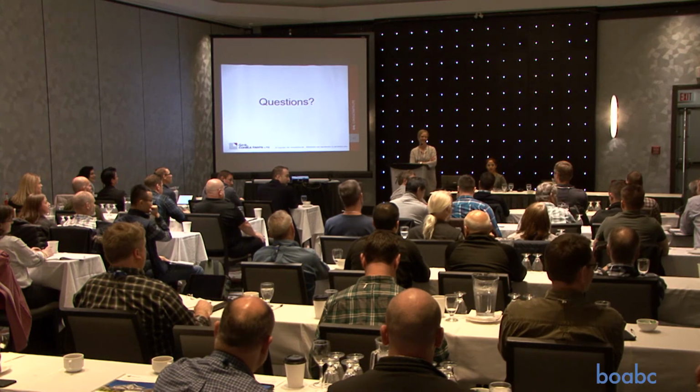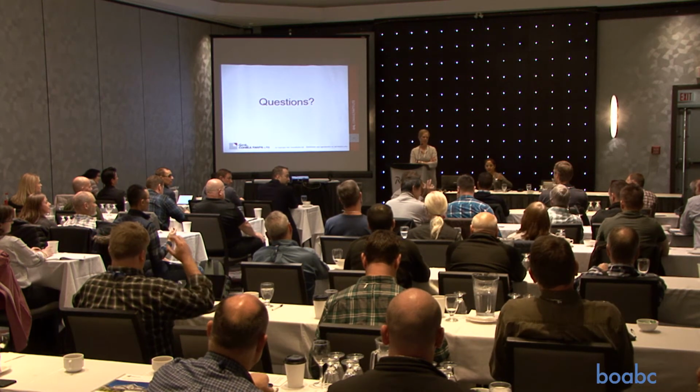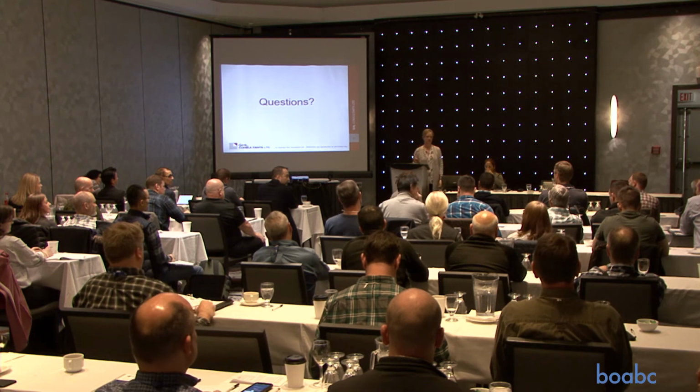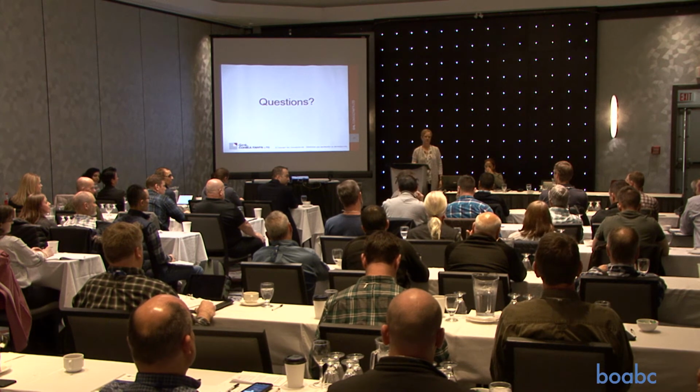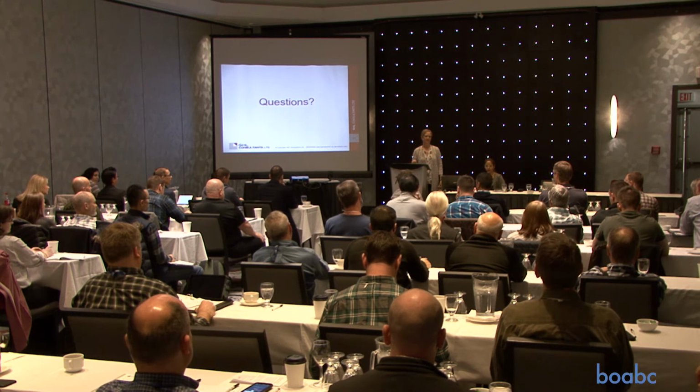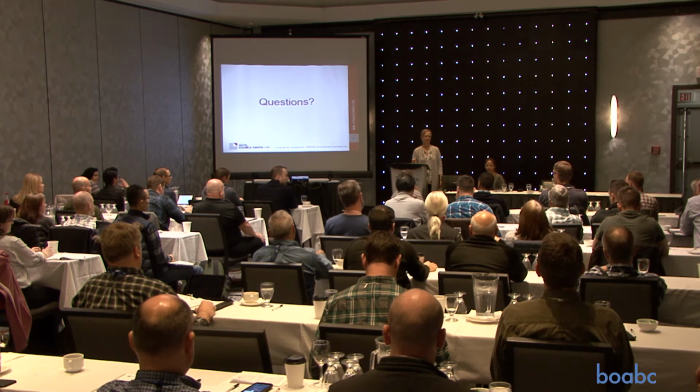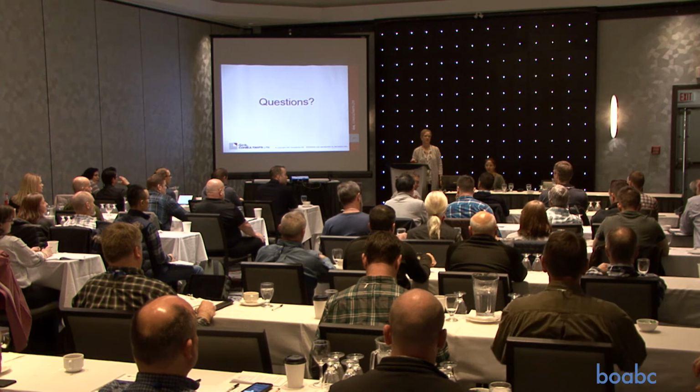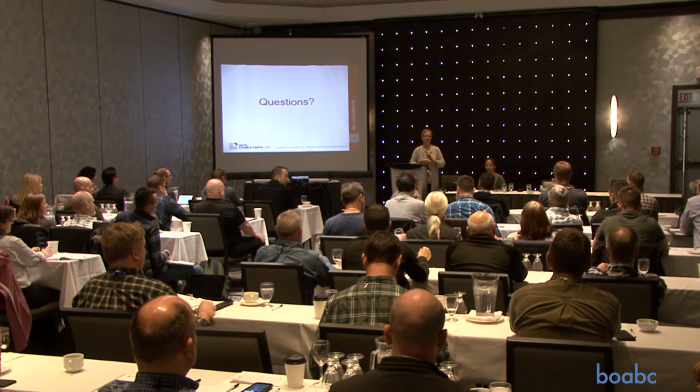Do you have rated T-bar ceilings? They're claiming they're rated T-bar ceilings. Ooh. I've seen a lot of rated T-bar ceilings on old drawings and in old buildings, and 30 years later, they were not rated at the beginning, and they're certainly not rated now. They've changed out a whole bunch of it.